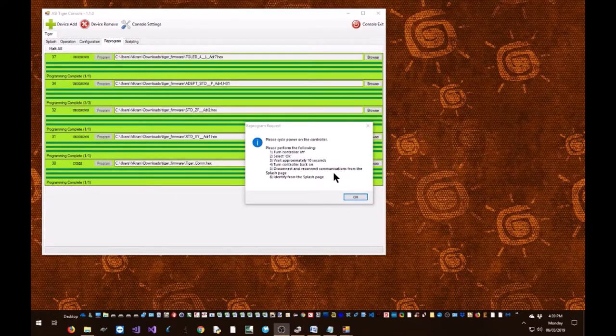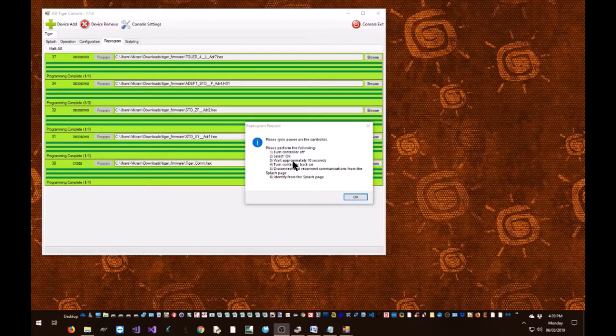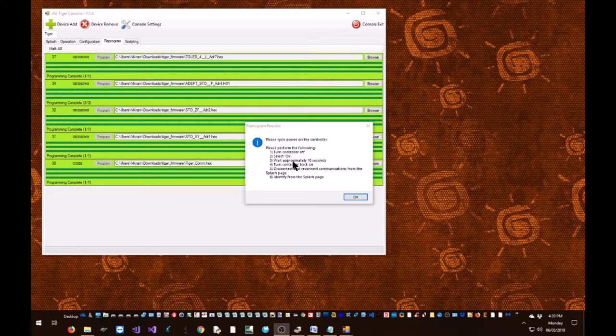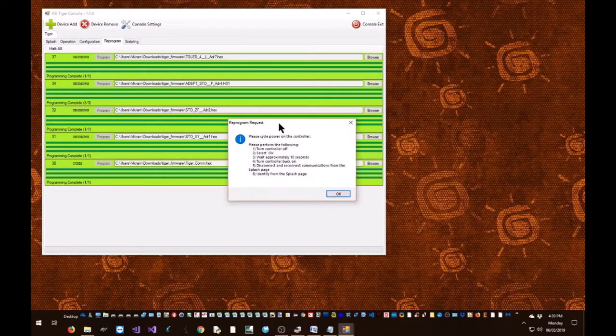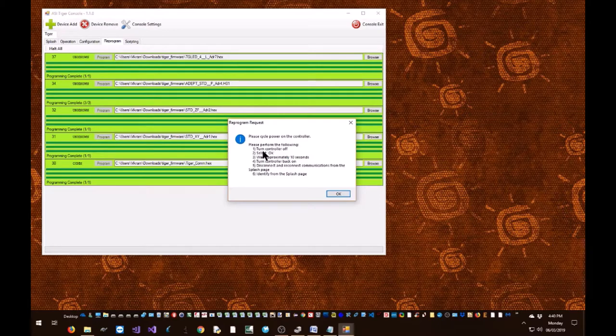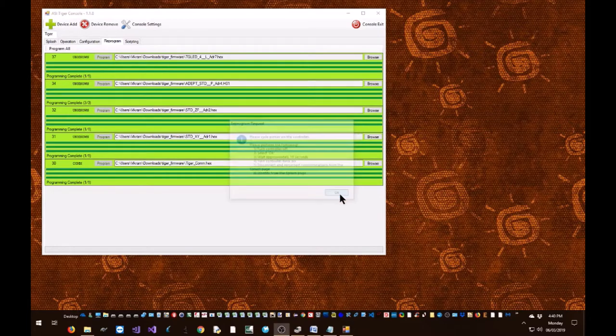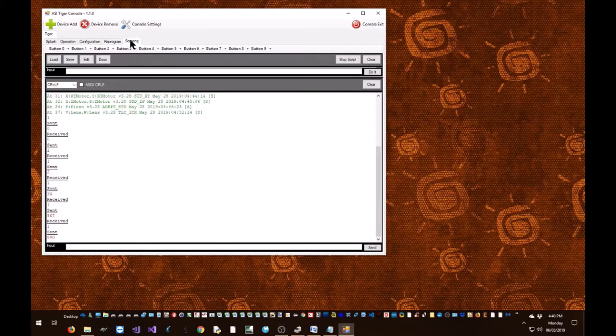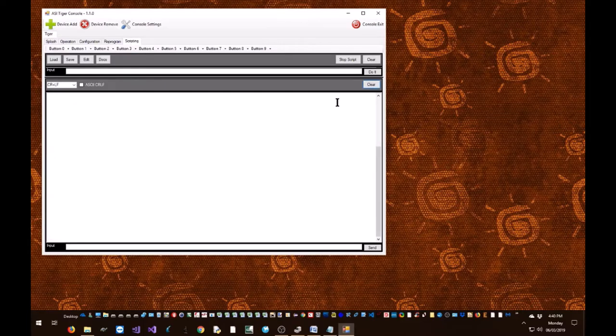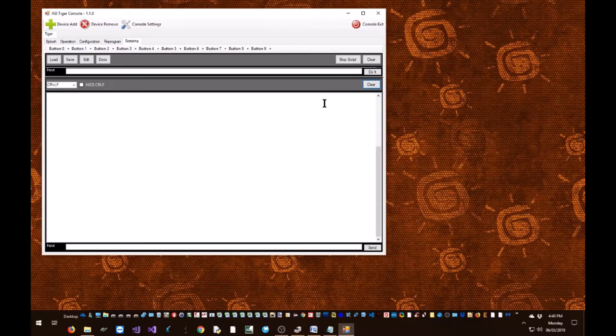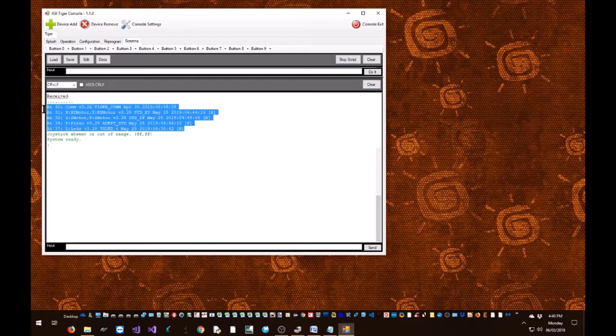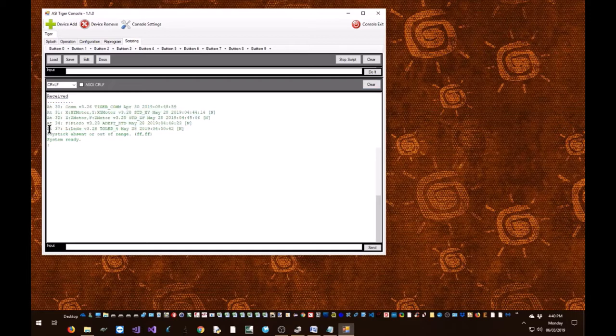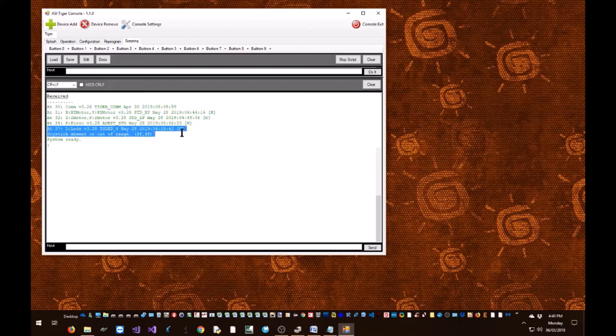Welcome back. It's been about 5 minutes and the Tiger console has finished loading all the firmware into the cards, and the following message has popped up. In order for us to use the system, we just need to turn off the controller and restart it again. Click OK. I'm gonna switch over to the scripting tab, clear out, and then turn off my controller, wait a few seconds, and then turn it on. There we go. All our cards are loaded up with new firmware and we even fixed the issue where we had the wrong firmware on our LED card.